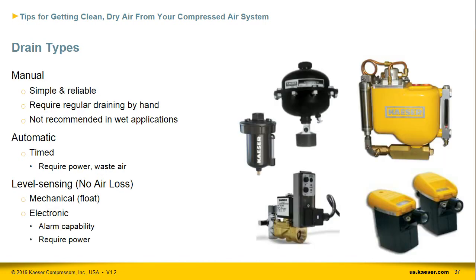Manual drains are inexpensive, simple, and reliable. At the same time, they're only as reliable as the memory of the person tasked with draining. They can be left partially open, but doing so is really only suitable for very small uses, like pilot air filters that will only see a few cubic feet per hour, since the drain will be continuously wasting compressed air. Manual drains are best suited to dry filters and tanks, where they're used for inspection and depressurization before service.